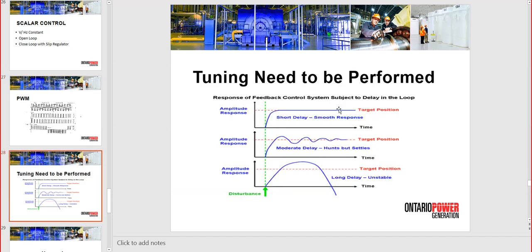Tuning, yes, vector is always closed loop control and needs tuning, after doing the parameter identification. So the first thing a vector control will do, it will read the motor by performing a cycle that is not under your control. You just say quick start and the motor will turn fast, slow, forward, reverse. After finishing the cycle, let's say it takes a few minutes, it will have all the internal parameters already read, and then it's going to correct with the temperature, the resistance, to have a good motor model in order to calculate the required control for the magnetization and torque.